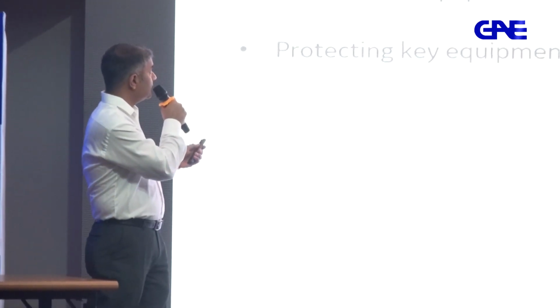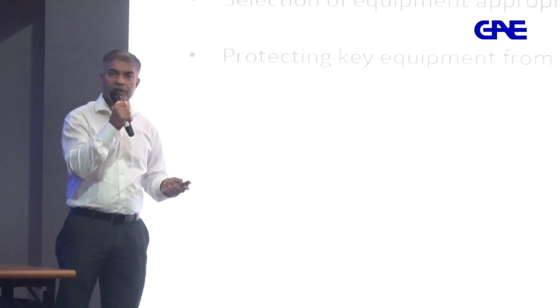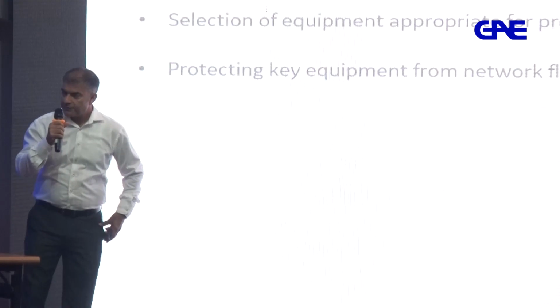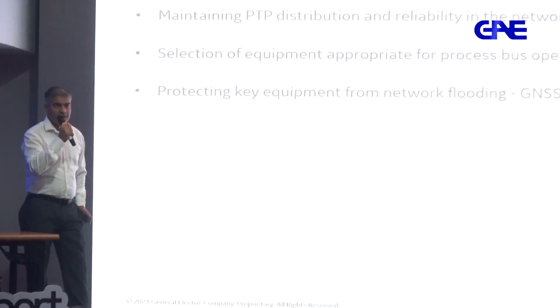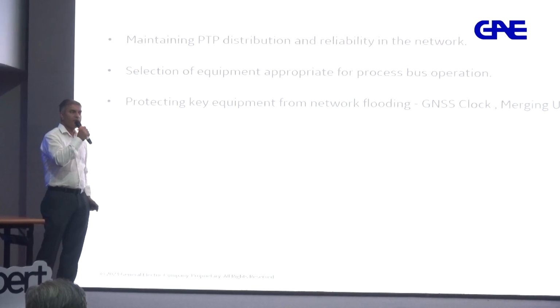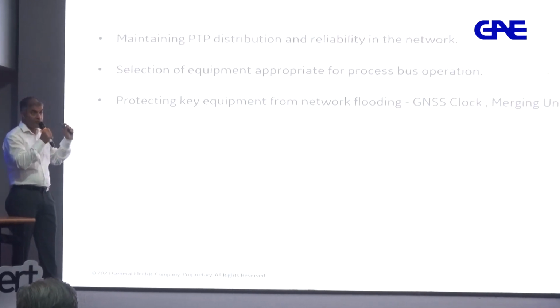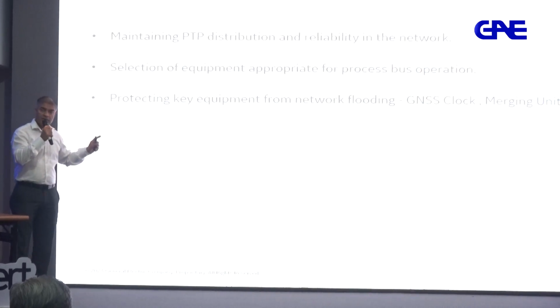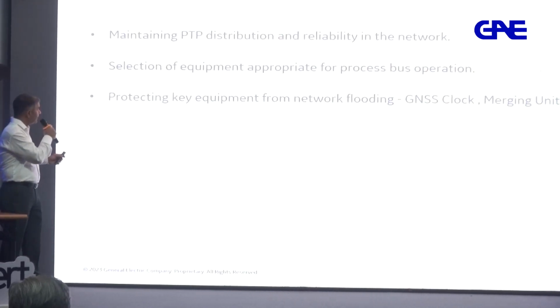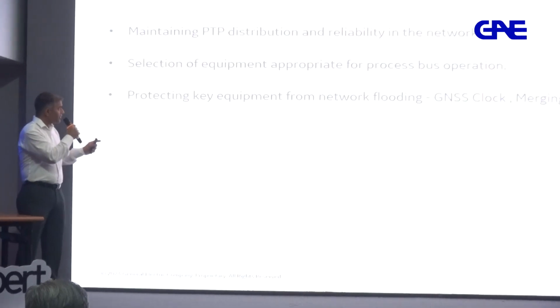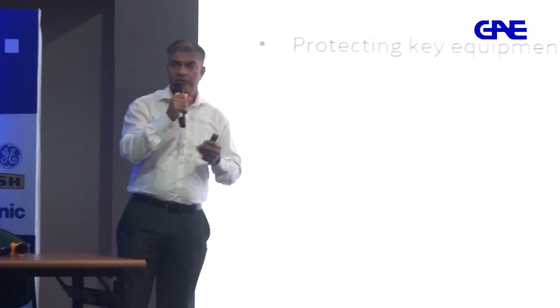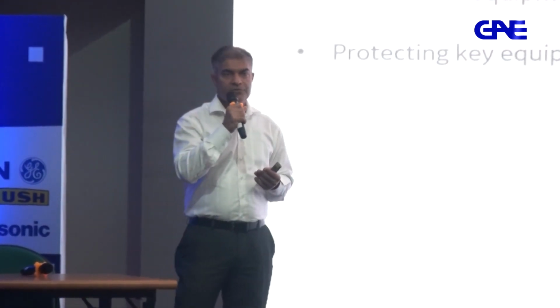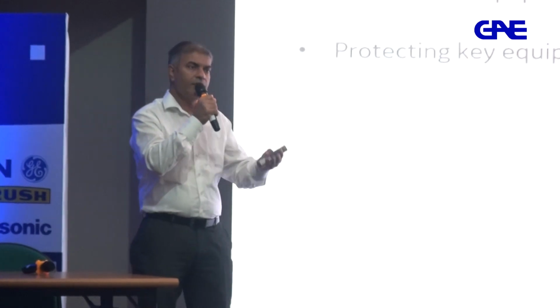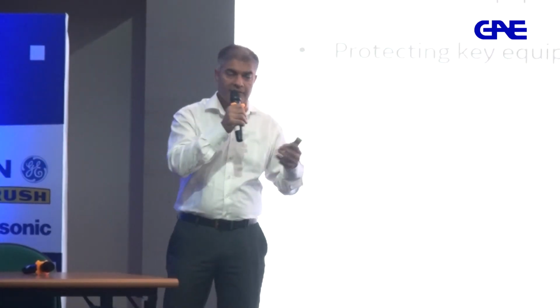Some of the things that we learned through different experiences is that you need to be careful about PTP distribution, because for process bus, time synchronization is very, very important. So you need to pay very particular attention to the PTP distribution and how well the time synchronization works in your substation. Selection of equipment appropriate for process bus operation. Obviously your switches should be able to support PTP, and should be able to support PRP in a way that it should support jumbo packets and all of that.